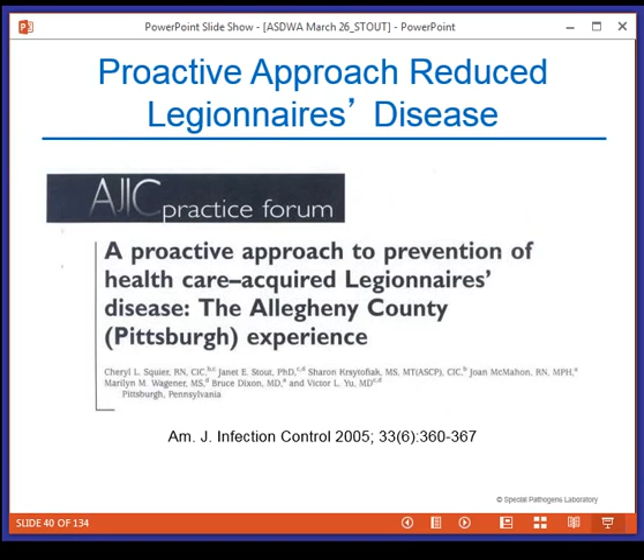You start by testing the water system—did you find Legionella, particularly Legionella pneumophila serogroup 1? If yes, were there any cases associated with this facility? If the answer is yes to both, you want to consider disinfection now. If there are no prior cases, is the water distribution extensively colonized with Legionella? Meaning, if you take 10 water samples from 10 sites within the hospital, are more than 3 of those sites more than 30% positive? If yes, you're likely to see cases of Legionnaire's disease. If no, you don't give up.